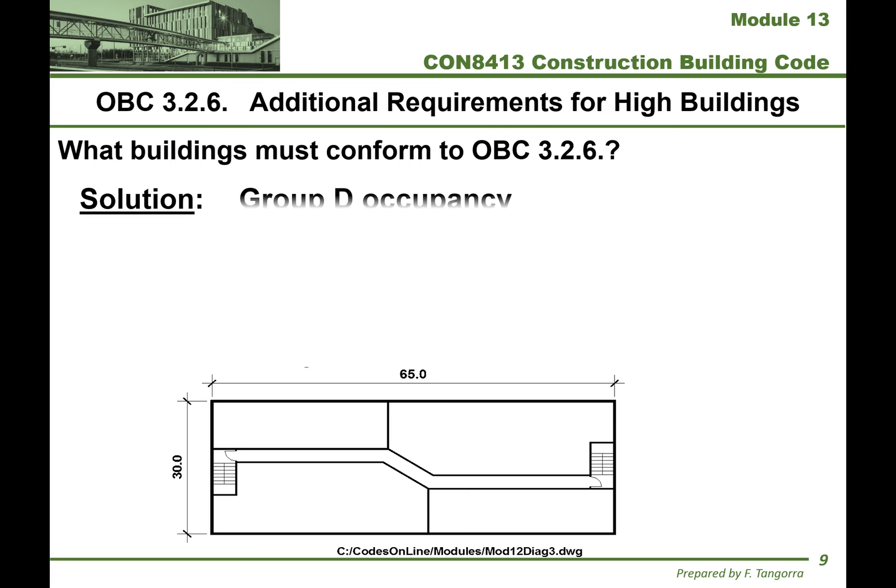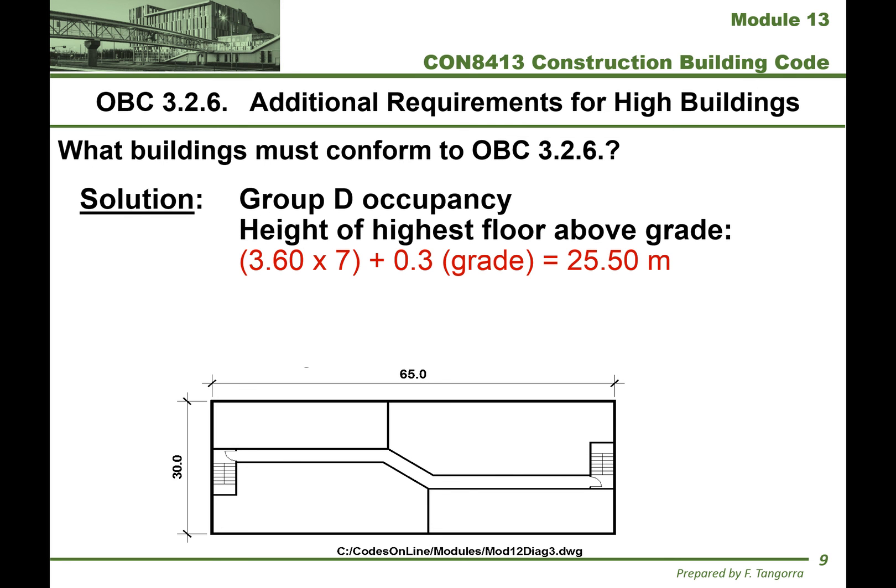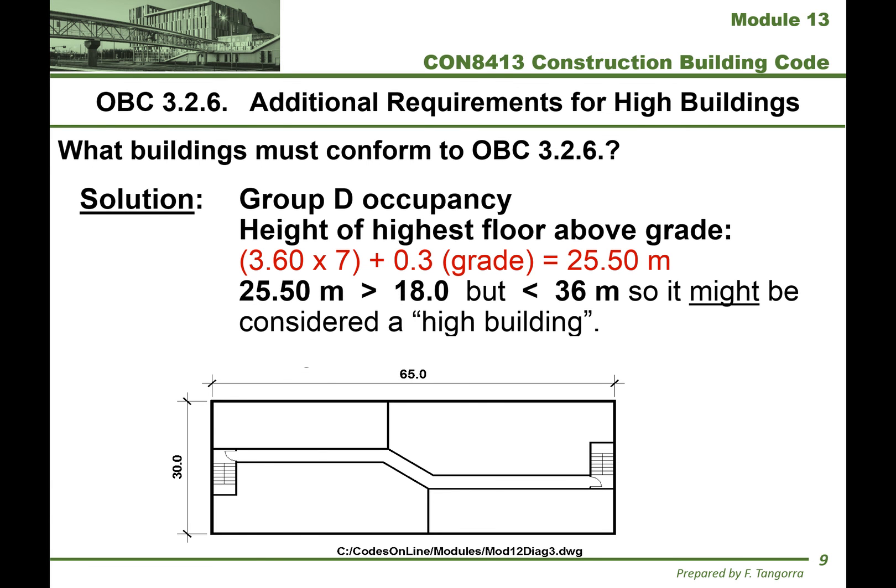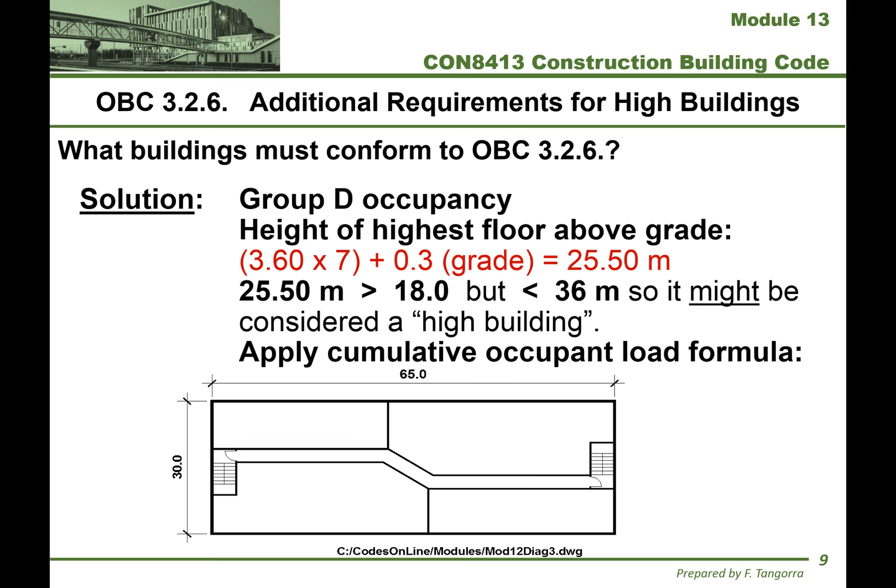Here's the solution. Based on its occupancy, this would be group D. If we calculate the vertical distance between grade and the top floor, it's 3.6 meters — the typical floor-to-floor height — times seven stories, not eight, because we're going to the top floor level, not ceiling level. Plus 0.3 meters of grade gives us a vertical distance of 25.50 meters. 25.5 is more than 18 but less than 36, so this building may be considered a high building, and we must use the formula to figure out whether or not it qualifies.